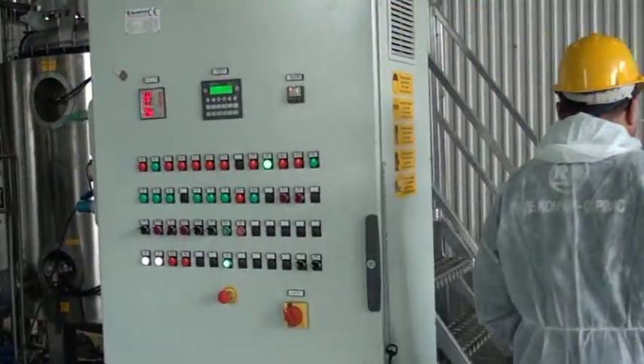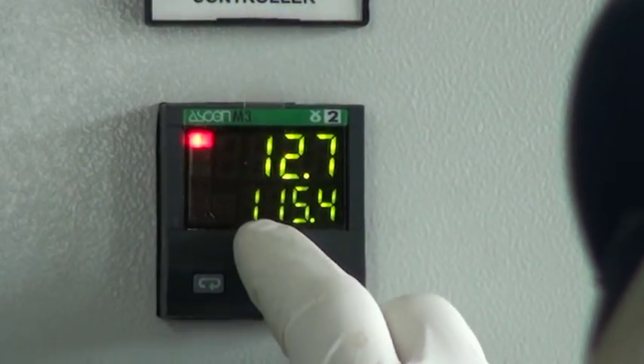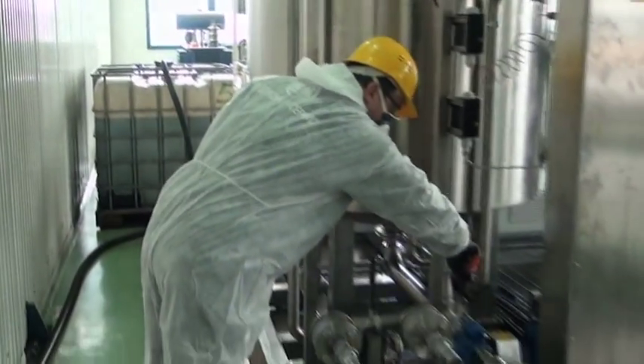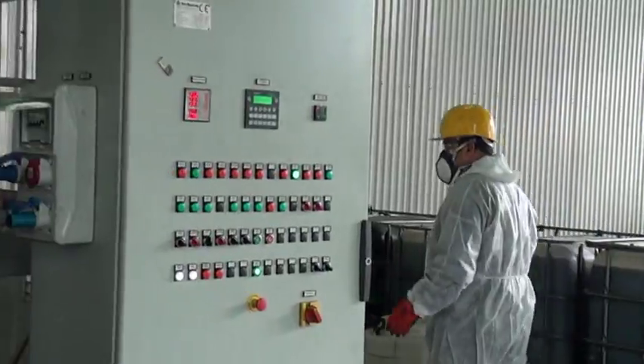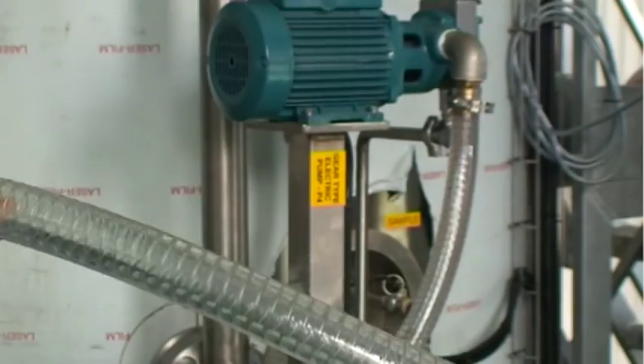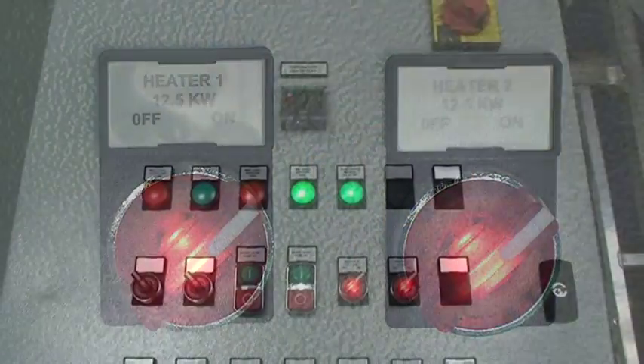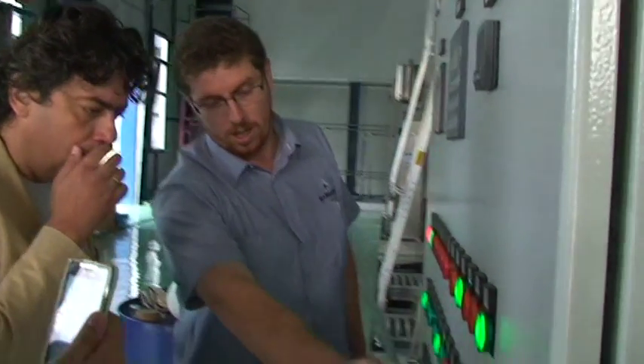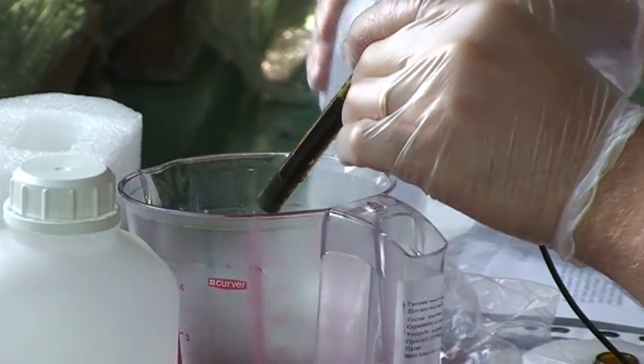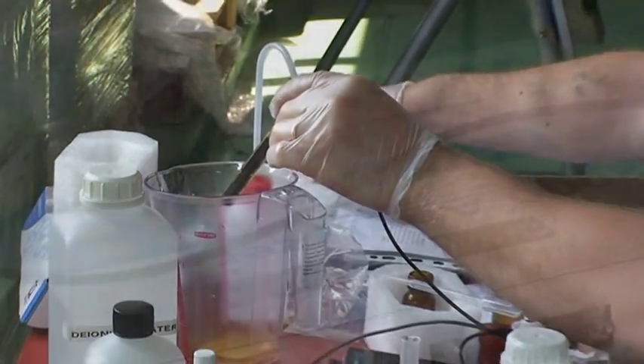Dehalogenation reaction. PCB-containing mineral oil is pumped by a hydraulic pump from the containers into a steel reactor, where it is heated at 100 to 110 degrees Celsius, stirred and mixed with a chemical reagent. Depending on the initial PCB concentration, the reaction could last for several hours. Process monitoring. The success of the treatment is monitored by measuring the total chlorine content of the oil using a Dexsil L2000 analyzer.